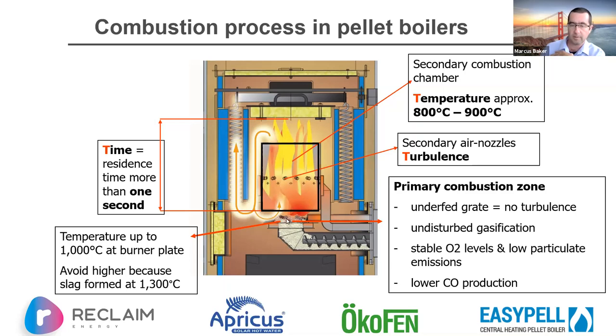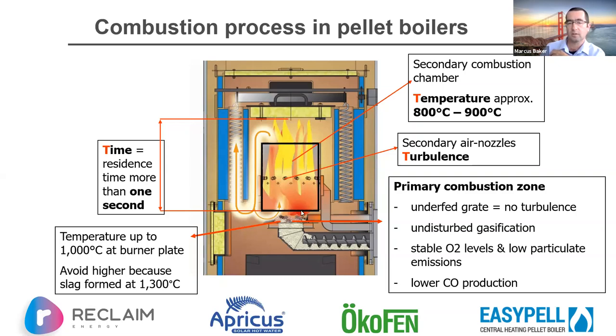You don't have fuel dropping onto the top or being pushed from the side. Dropping from the top is potentially a bit more problematic in disturbing your ember bed. You've got gasification occurring at very stable levels of oxygen, meaning you get low particulate emissions and also low carbon monoxide production, which is important.